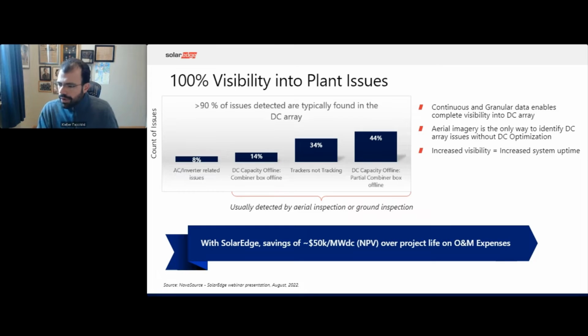I presented a webinar with NovaSource in the middle of 2022, and a data set shared by them is that greater than 90% of the issues happen on the DC side of the plant, and these are typically detected only via an aerial inspection, which happens once or twice a year. Module level monitoring enables continuous and granular data, which allows issues to be caught early and provides the asset manager the tools to determine whether and when a crew needs to be dispatched.